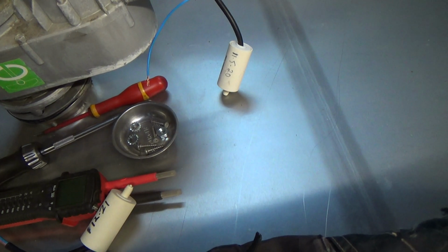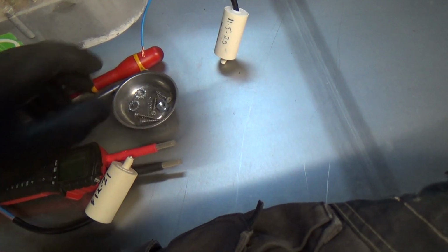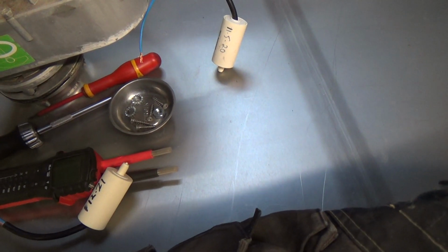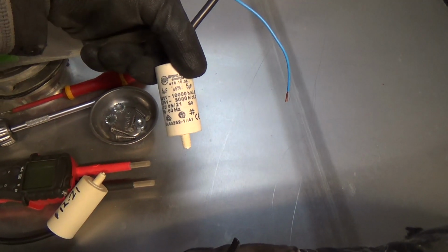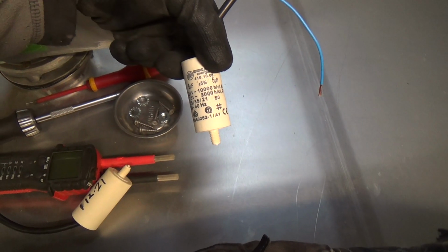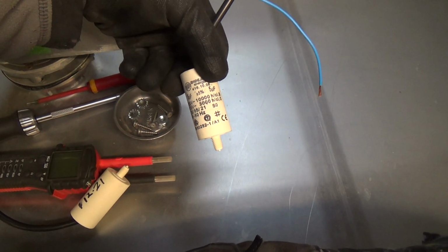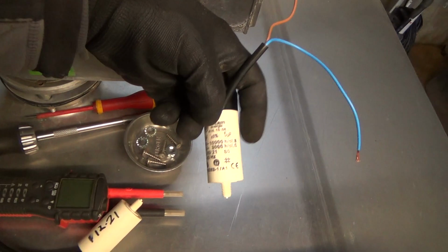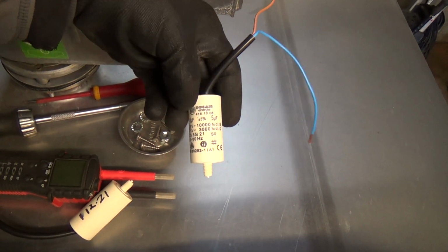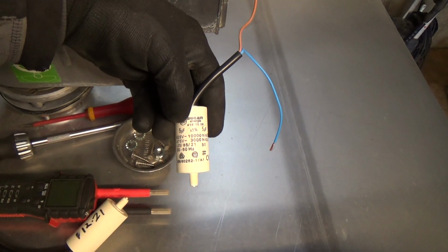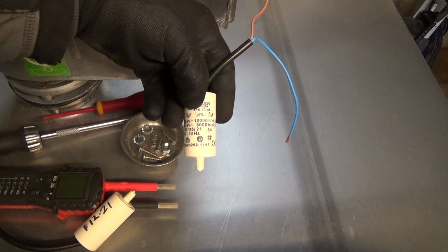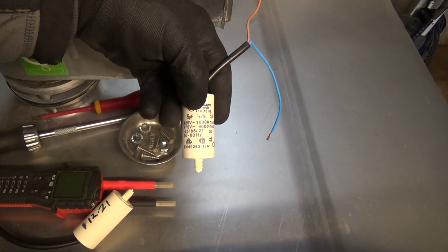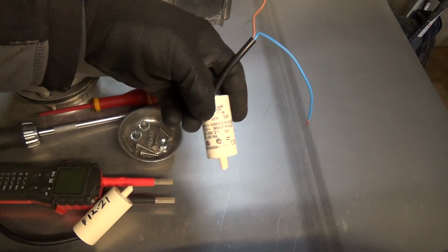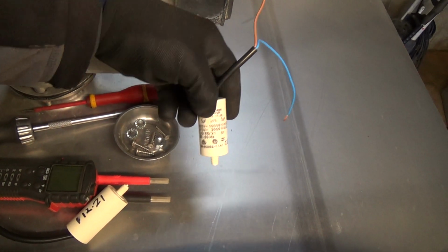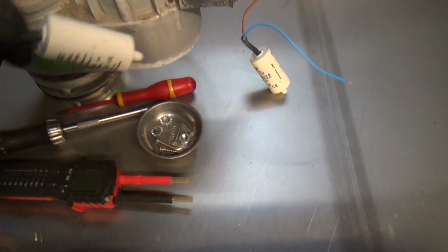Right, tested the capacitor on the chilled water pump, and that was fine still. But the one on the agitator is showing, should be a 5, and it's showing 4.5. So it's 10% out. There's 5% tolerance, but I take that as a manufacturing tolerance. So if it was 4.75 when it was new, that's good. Or it could be 5.25 and it's still within spec. But it should stay at that for most of its life. When they start dropping is when they're wearing out.